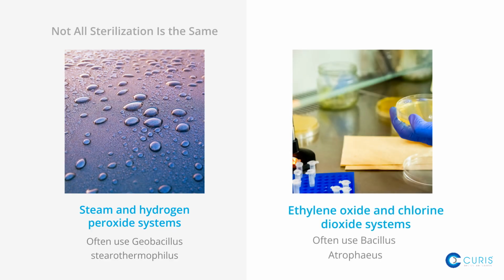The hardest organism to kill depends on the sterilization method, and different technologies require different challenge organisms. Steam and hydrogen peroxide systems often use Geobacillus stearothermophilus. Ethylene oxide and chlorine dioxide systems use Bacillus atrophaeus. Validation always matches the organism to the chemistry being tested, ensuring a true worst-case challenge.